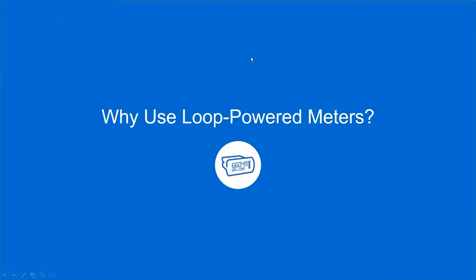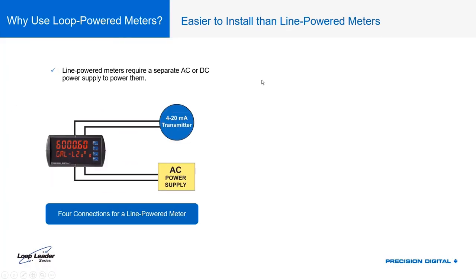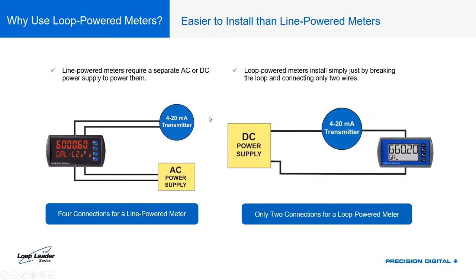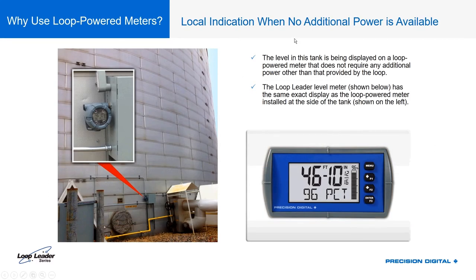Why do people use loop power meters? The most important reason is that they're easier to install than line power meters. A line power meter like the ProView has a 4-20 milliamp input but requires a separate AC or 24-volt power connection — making it a four-wire meter. By contrast, a loop power meter lets you just break the loop wherever you want to put the meter and connect those two ends directly. There's less wiring and fewer parts involved.